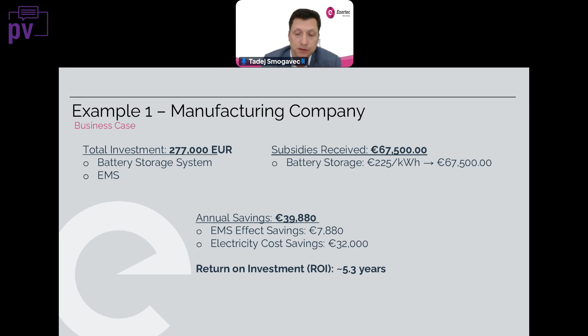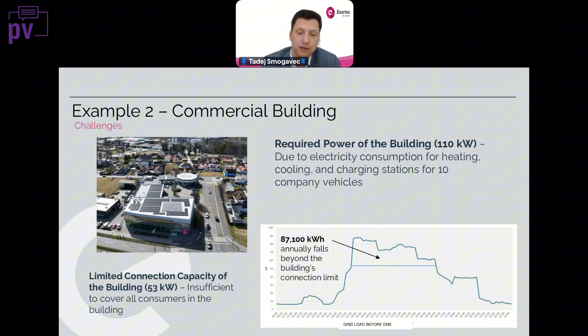And the second example is the commercial building, with a little bit different challenge. We have a required power of the building of 110 kilowatts, mostly because of the 10 charging stations required for the electrification of the fleet within the company. But the building had only 53 kilowatts of power capacity. So on the chart, you can see that with these requirements, we had a lack of almost 90,000 kilowatt hours of electricity annually.